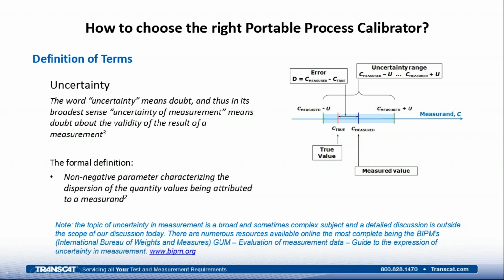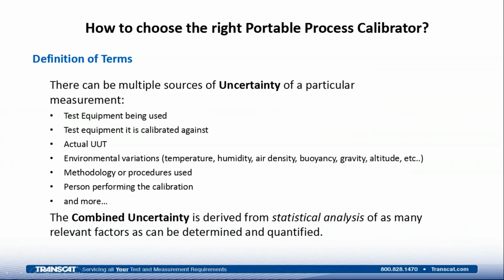But for the purposes of our conversation, I just want to make the distinction between how calibrator performance is defined versus how device measurement performance is defined. There can be multiple sources of uncertainty for a particular measurement. There's uncertainty associated with the test equipment being used, and with the test equipment that test equipment is being calibrated against. The actual unit under test has uncertainty associated with it. There are uncertainty contributions from environmental variations: temperature and humidity, air density, buoyancy, gravity, altitude, others. There can be uncertainties from the methodology or procedures being used. It can be down to the person performing the calibration. And there can be other potential contributions of uncertainty to the measurement.